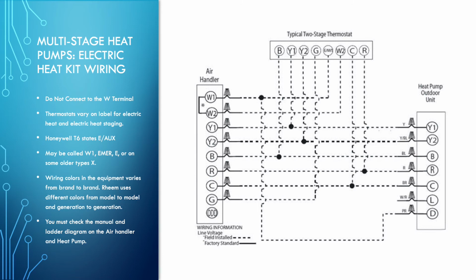when you install it. Now, other terms that you might see on thermostats are W1, as you see in this one, EAUX, which is auxiliary. I hate saying that word. You might also see the word EMER for emergency spelled out, or just the letter E. I've seen some Trane and older thermostats will often use the letter X to dictate emergency heat or the electric heat kit. Once again, you got to check the ladder diagram for the equipment you're putting in, whether it's Goodman or if it's Rheem, whatever you're working with, focus on what they have their wire set up.